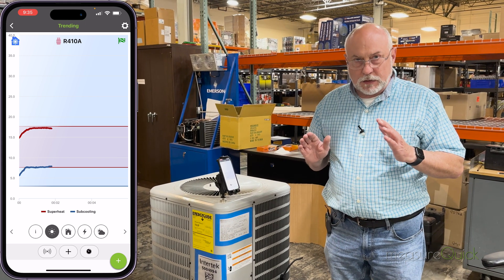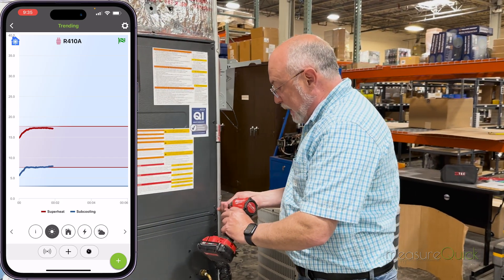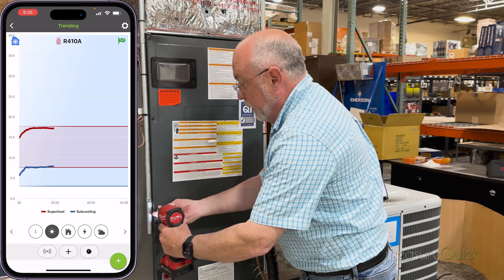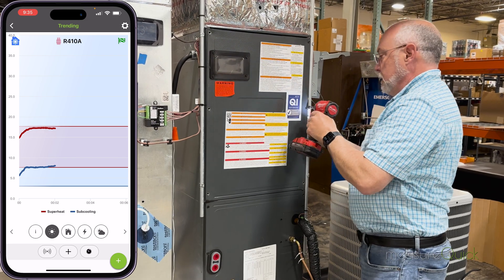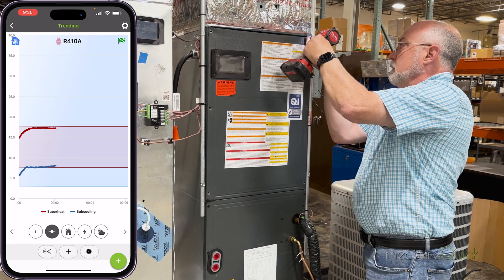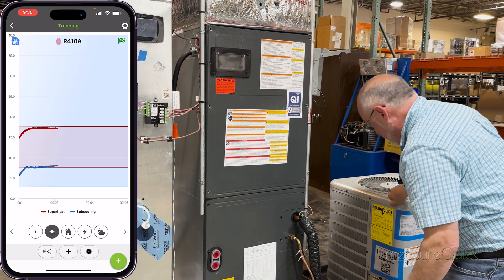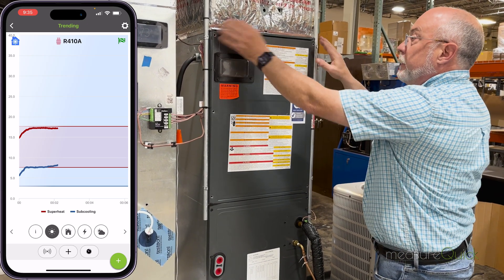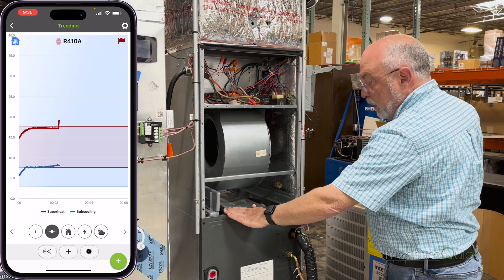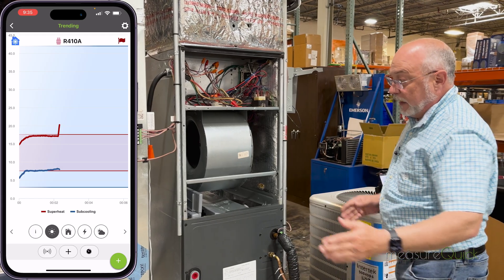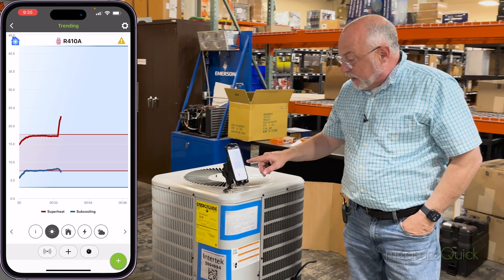Now we're going to create what we're going to call a low airflow situation. What I'm going to do is go ahead and just pull the door off the air handler. What's going to happen is all the air is going to be pulled straight into the fan and we're going to bypass the coil effectively. All the air is just going into the sides here — no air is going through the evaporator coil.